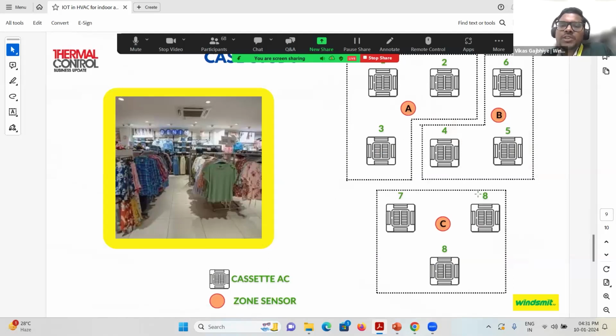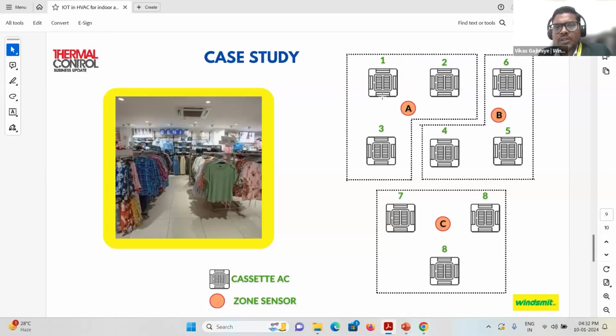There were 9 cassette units contributing to a common area and maintaining the indoor air temperature. But because of sensor degradation, there was no proper decision-making for powering down particular cassette units.